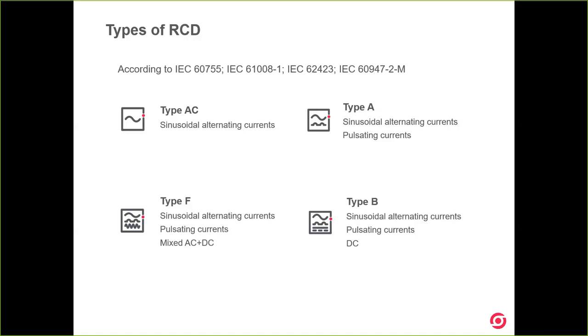The symbology is very intuitive because we can see what kind of protection each type of RCD can offer. Let's start with the most basic one and go to the highest. The most basic is type AC, which can only protect against sinusoidal alternating current. Next is type A, which can protect sinusoidal alternating current and pulsating currents. Then type F, which can protect sinusoidal alternating currents, pulsating currents, and mixed AC and DC. As you can see, each type adds the features of the previous ones.